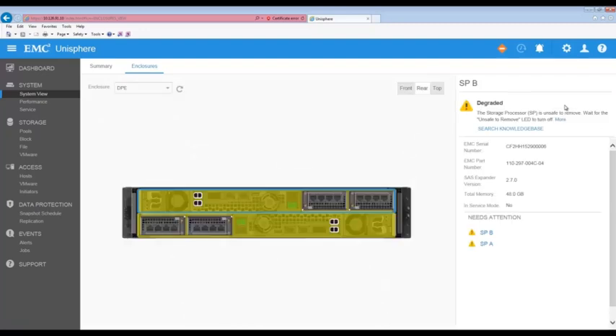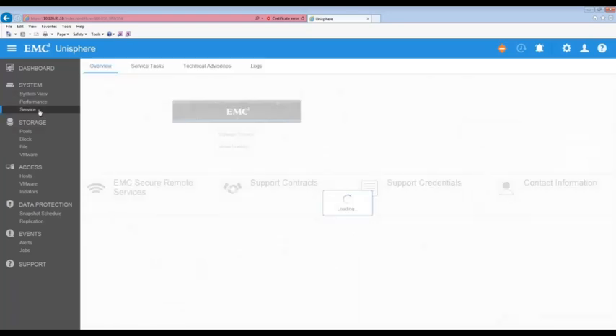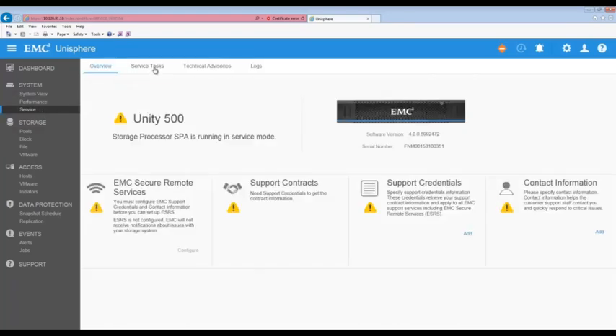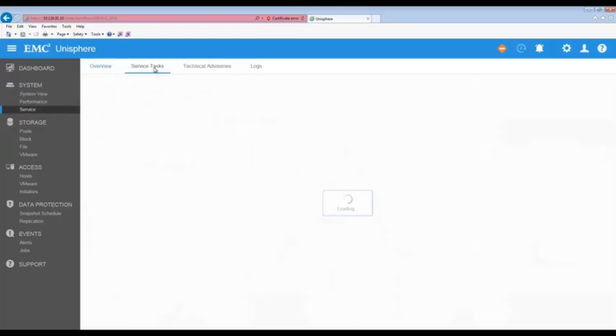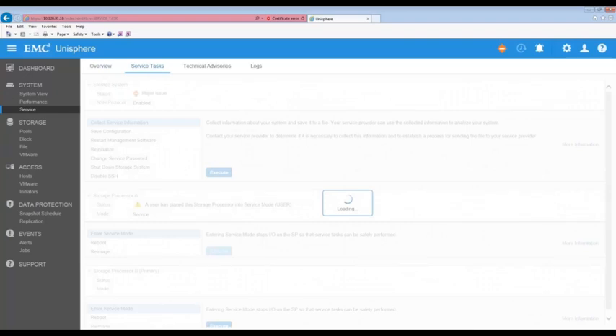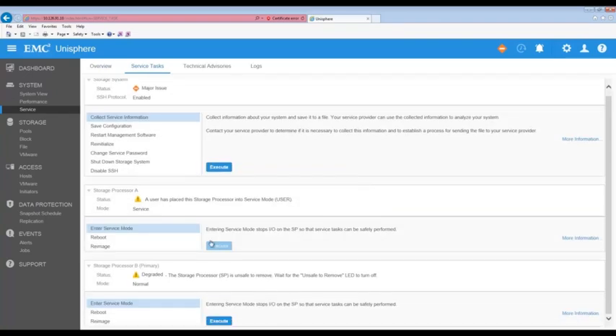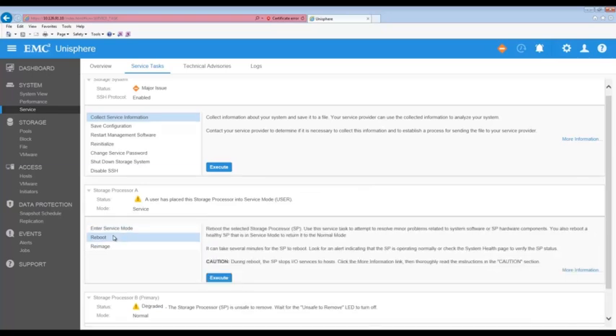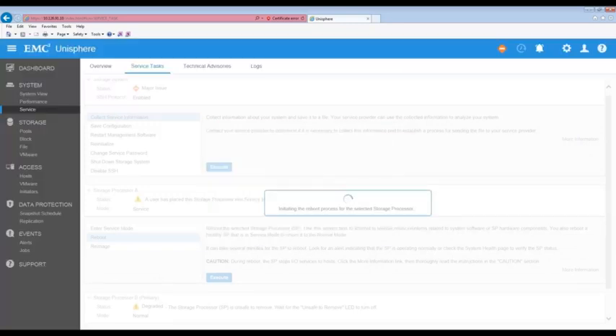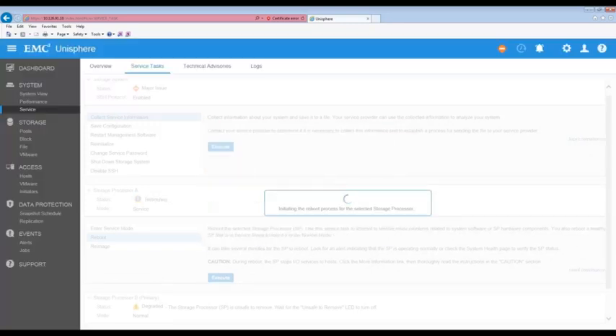Since these are both expected errors we can now go back to the service task page and reboot SPA. This action will reboot SPA into normal mode. Select reboot for SPA and then click on execute. When prompted enter the service password. Note that it may take up to 20 minutes for the system to complete its reboot and return to normal.